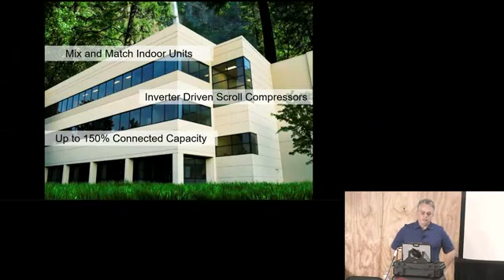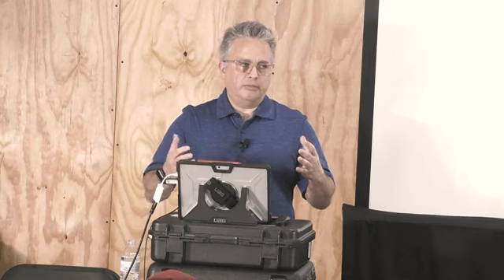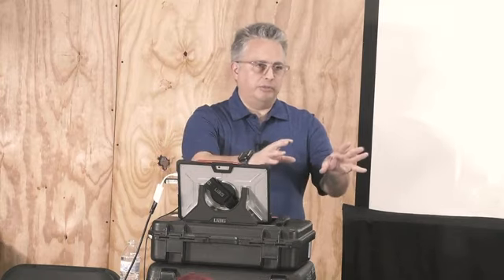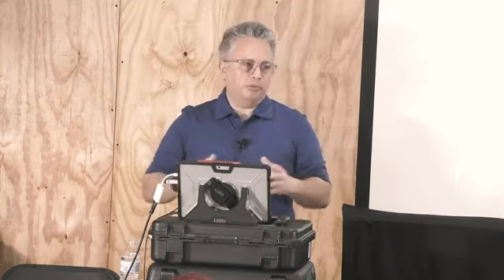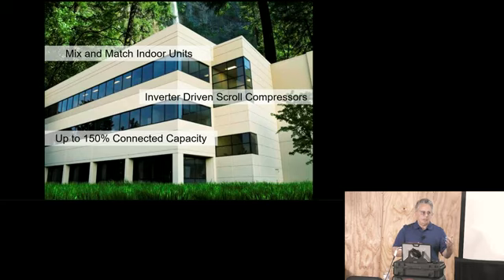Now, my personal experience is that you really don't want to go any more than maybe 10 or 12%, something like that. But you really have to know your building well to strategize what is called diversity, right? Because a building is not 100% used all the time. There's sections, people move around houses, right? In the daytime, in the nighttime, people are in the bedrooms. At nighttime, people come out. Same thing with a commercial building. So there are some assumptions that you can put into your design. But like in Phoenix, Arizona, there's no diversity. It's just hot. So be careful.